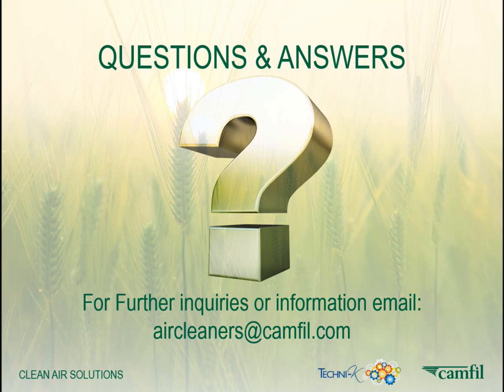I agree. For me, it's two different ways. One thing is what is the quality inside the room, and what is actually the quality supplied through the HVAC unit. One thing is the filter in the HVAC unit, which should be according to standard and reach the desired level. Then, of course, we should discuss what is the desired level. Is it F7, which is kind of 50% of the particles filtrated, or is it the HEPA filter that actually stops E. coli, for example? I don't know if that was good enough as an answer.